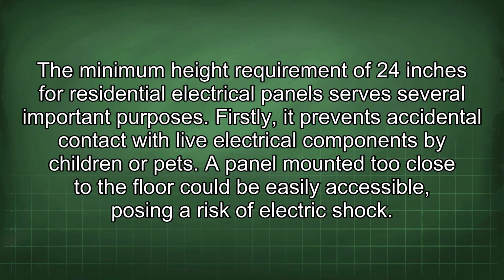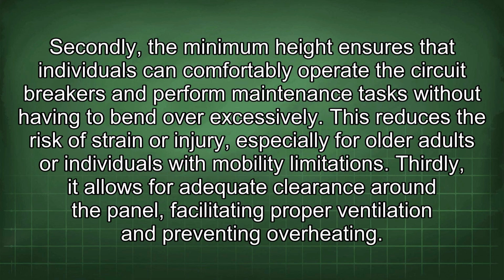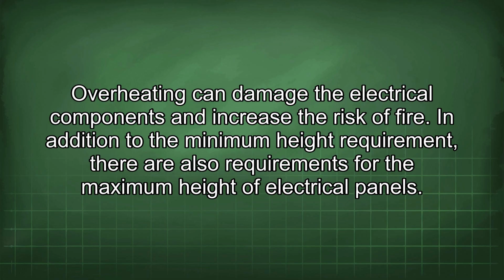The minimum height requirement of 24 inches for residential electrical panels serves several important purposes. Firstly, it prevents accidental contact with live electrical components by children or pets. A panel mounted too close to the floor could be easily accessible, posing a risk of electric shock. Secondly, the minimum height ensures that individuals can comfortably operate the circuit breakers and perform maintenance tasks without having to bend over excessively. This reduces the risk of strain or injury, especially for older adults or individuals with mobility limitations. Thirdly, it allows for adequate clearance around the panel, facilitating proper ventilation and preventing overheating. Overheating can damage the electrical components and increase the risk of fire.